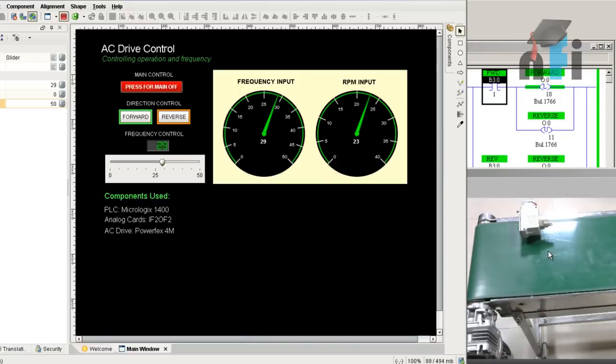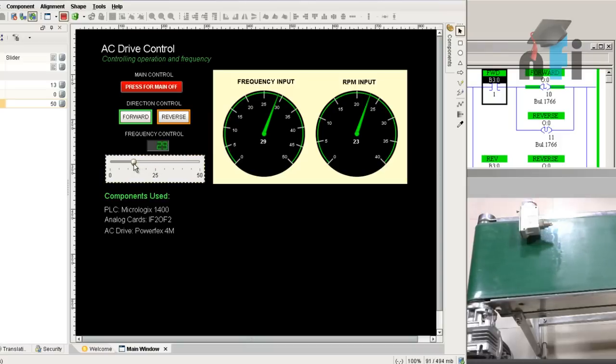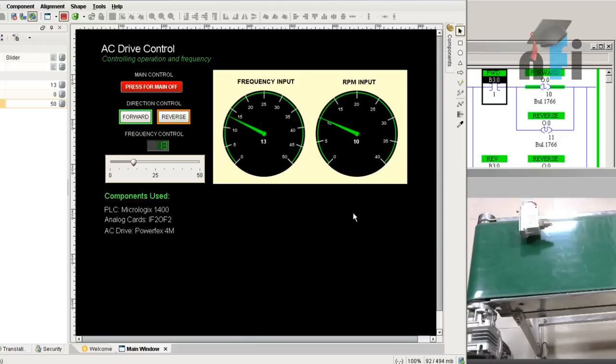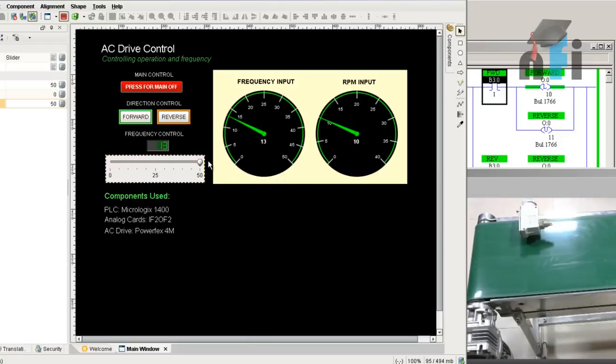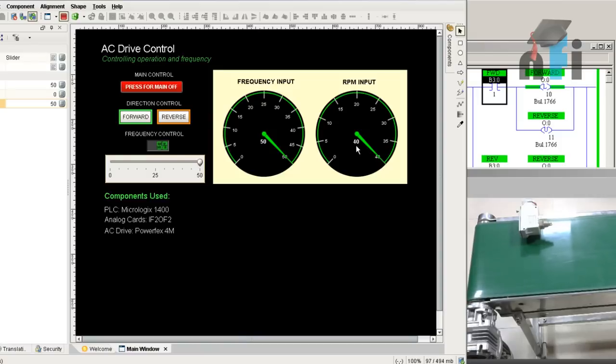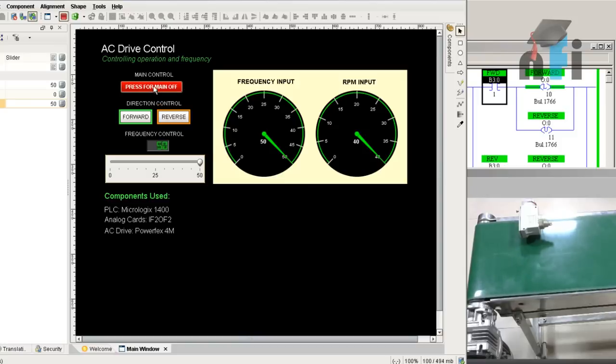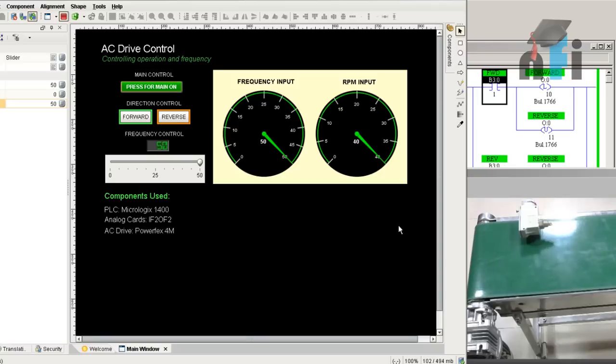If I want to decrease the frequency, it will decelerate to 13 hertz or 10 RPM. This is the gearbox. You can achieve maximum RPM by having 50 hertz which leads to 40 RPM, the maximum RPM of the motor. If you press this stop button, this will stop the drive. This is actually actuating and deactivating the outputs of the PLC.